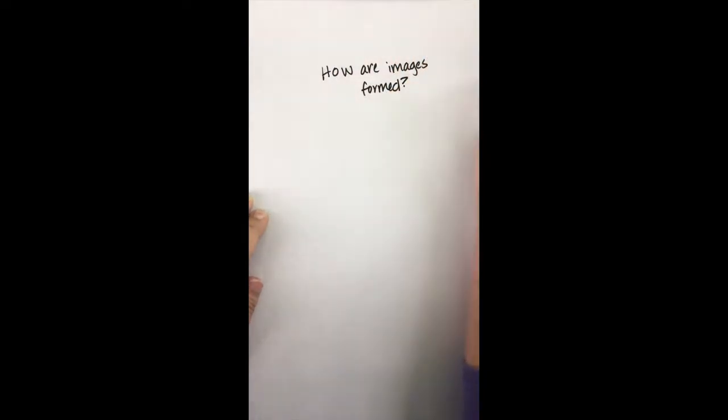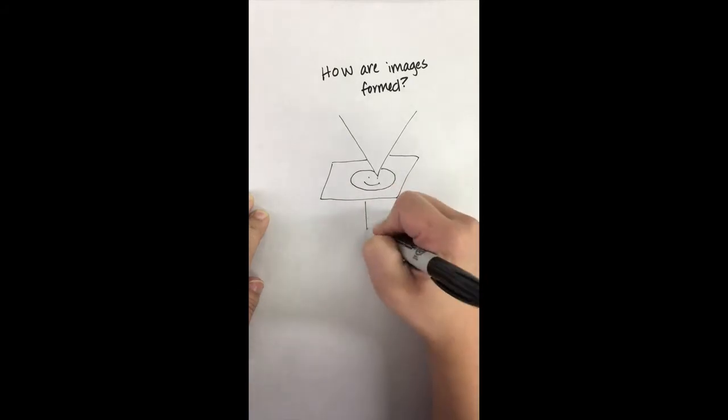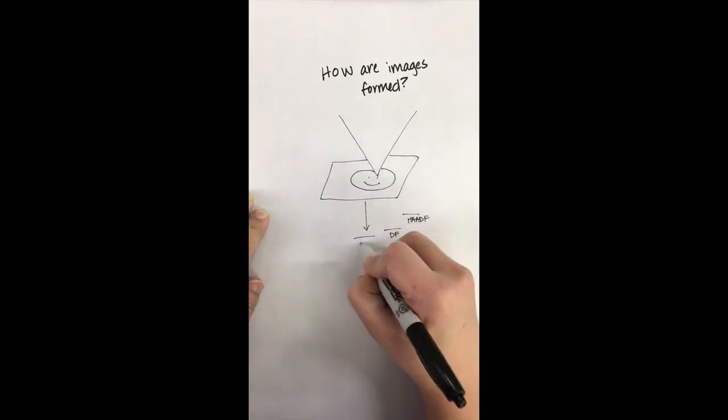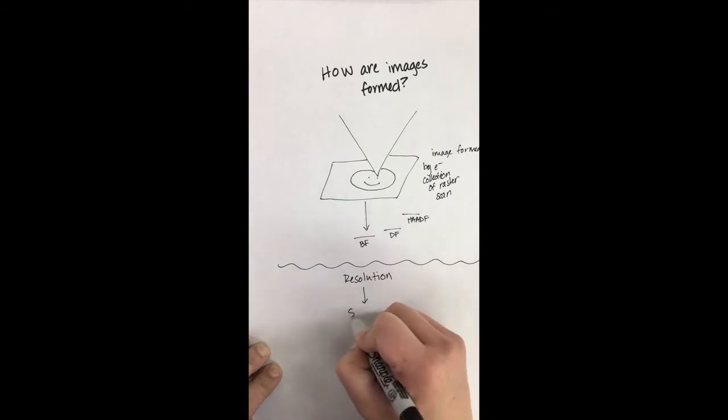Image formation in STEM mode comes from the fact that your sample interacts with the beam at a singular point. This point can be rastered across the sample and electrons collected at every single position of the beam by detectors. And so the resolution of a STEM image comes from how well the beam is focused, or the beam's spot size.